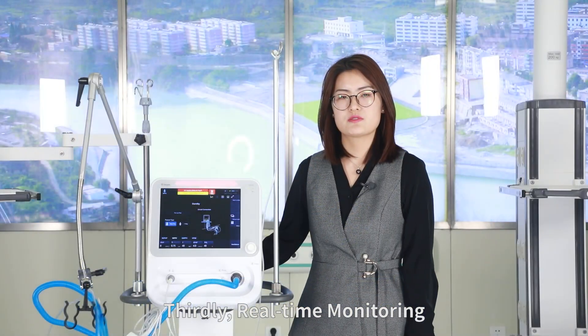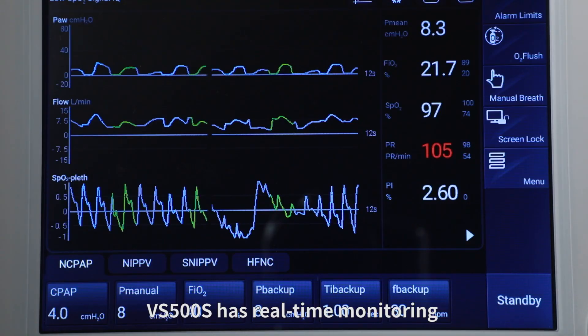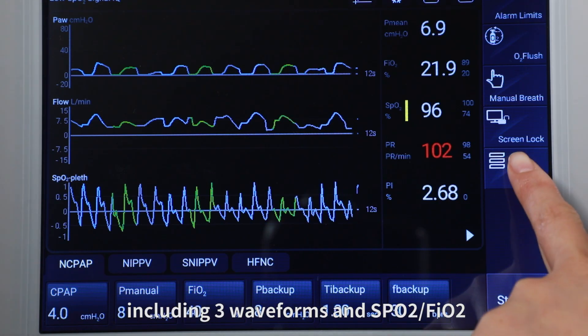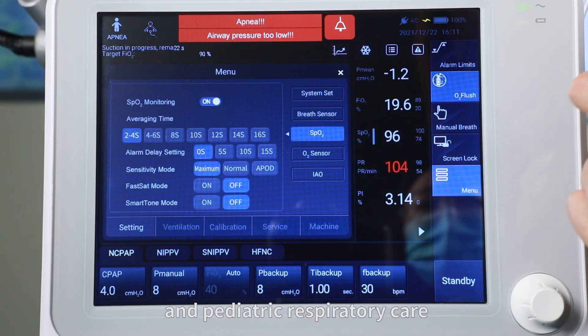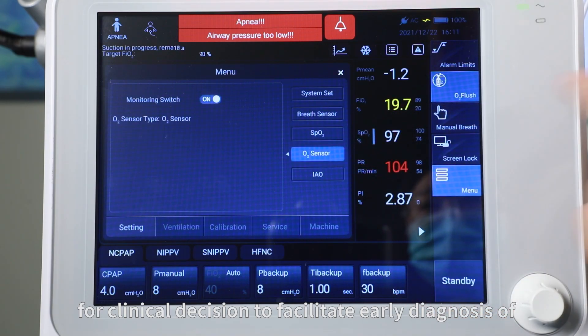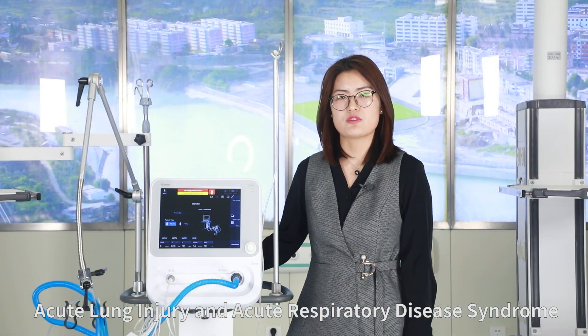Thirdly, real-time monitoring with a blood saturation module. The VS500S has real-time monitoring including three waveforms and SpO2/FiO2. It also displays perfusion index and oxygen saturation index to give more reference for clinical decision-making, facilitating early diagnosis of acute lung injury and acute respiratory distress syndrome.